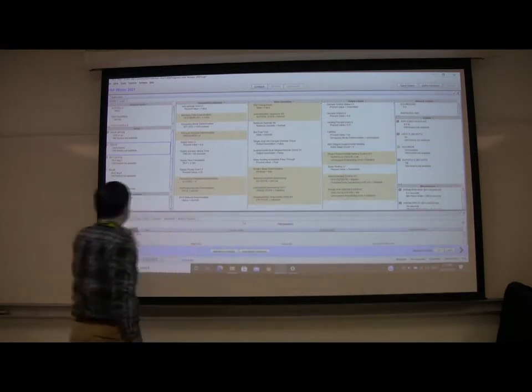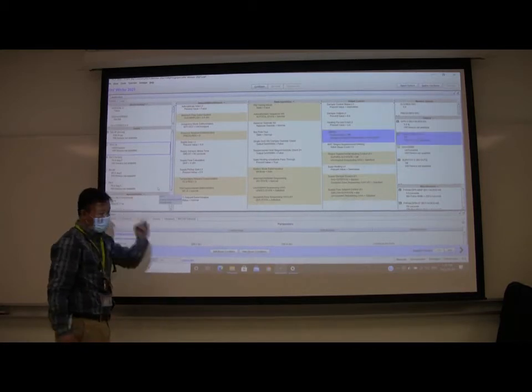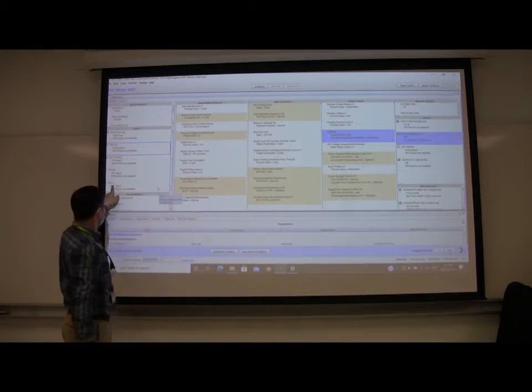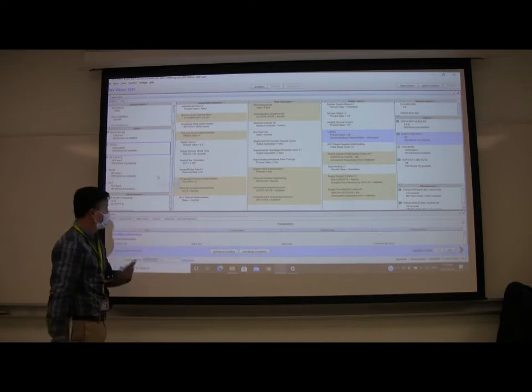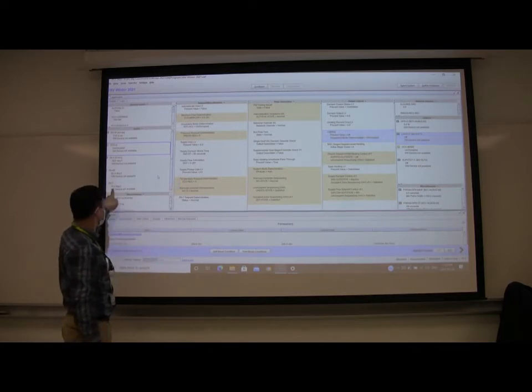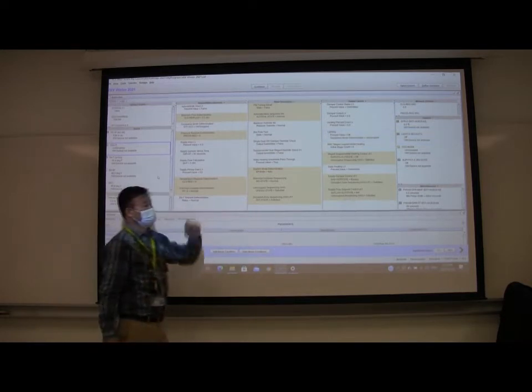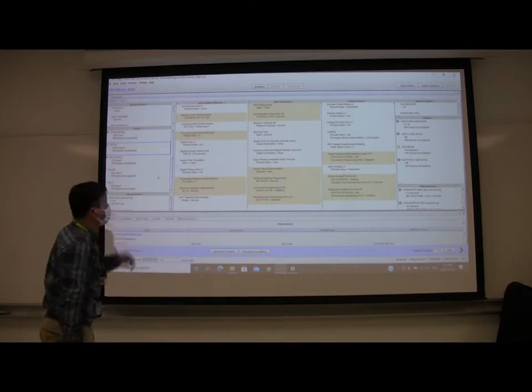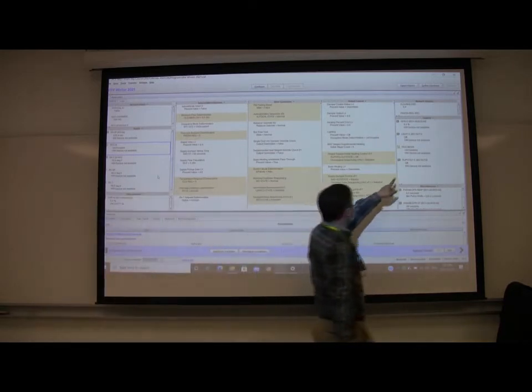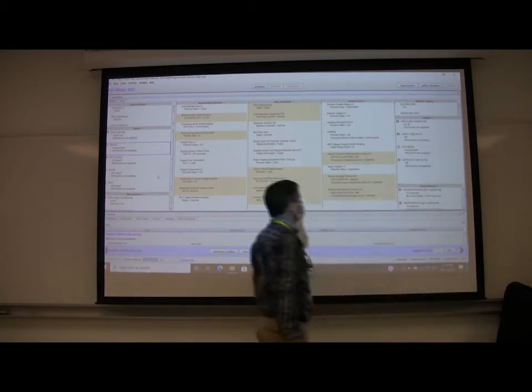Continue here. This one, if we set the temperature, the set point, if we set the temperature lower than this temperature, and then the heating should be off. You see, heating should be off. Here it's also because it's unoccupied, off, and then the system is off.